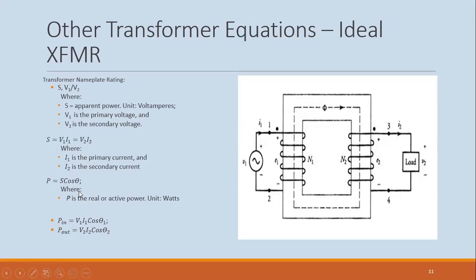Now, if you look at this circuit, P1, the real power, is equal to VI cos theta. So the input power would be V1 I1 cos theta 1, and the output power would be V2 I2 cos theta 2. Cos theta 2 is the load power factor. That's usually different from the power factor on the primary side because there are slight differences between the phase angles for the primary current and the secondary current. So the power factor angle is not the same on the primary side, but bear in mind, cos theta 2 is the load power factor.